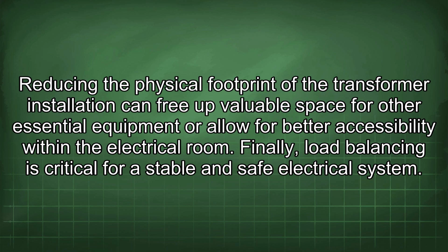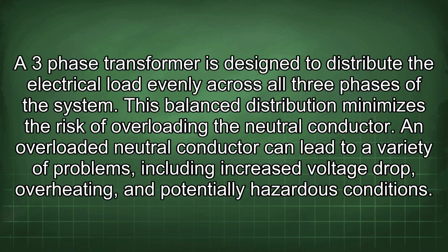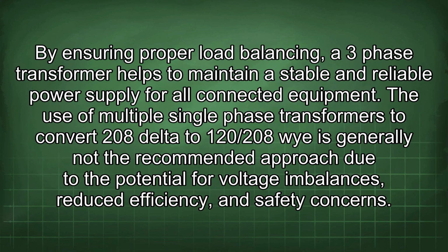Finally, load balancing is critical for a stable and safe electrical system. A three-phase transformer is designed to distribute the electrical load evenly across all three phases of the system. This balanced distribution minimizes the risk of overloading the neutral conductor. An overloaded neutral conductor can lead to a variety of problems, including increased voltage drop, overheating, and potentially hazardous conditions. By ensuring proper load balancing, a three-phase transformer helps to maintain a stable and reliable power supply for all connected equipment.